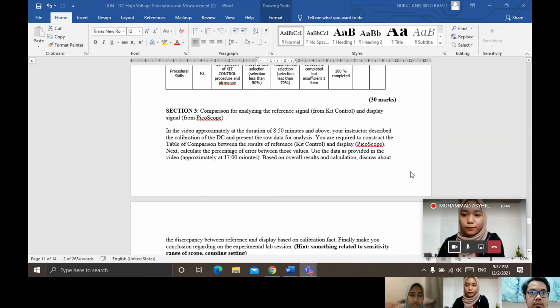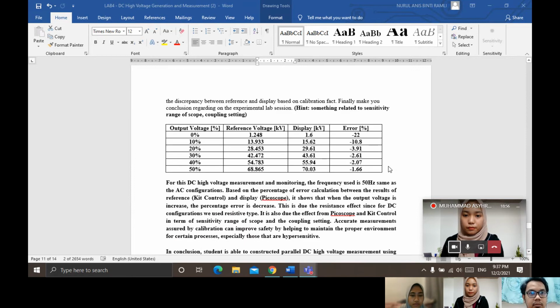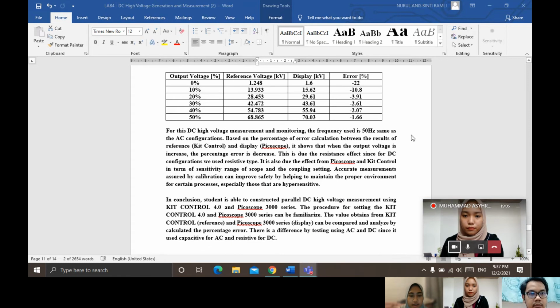Okay, my name is Nurul. I will explain section 3, which is the comparison for analyzing the reference signal from kit control and the display signal from picoscope. This is the value at the reference voltage and display, and this is the error. For this DC high voltage measurement and monitoring, the frequency used is 50 Hz, same as the AC configuration. Based on the percentage of error calculation between the result of reference, kit control, and display, which is picoscope, it shows that when the output voltage is increased, the percentage error is decreased.